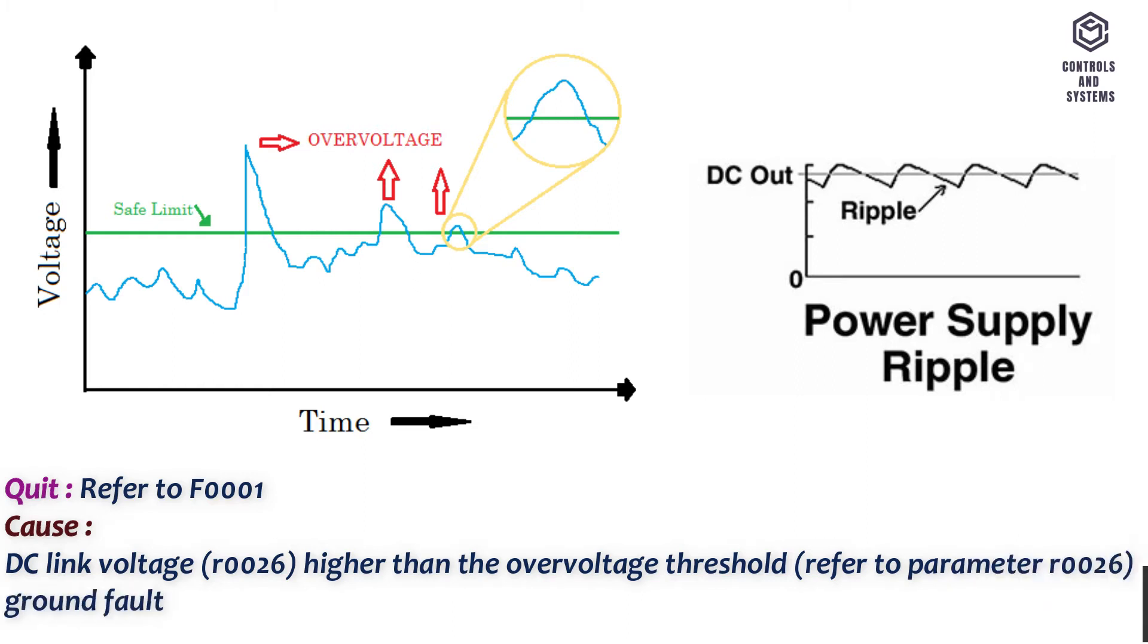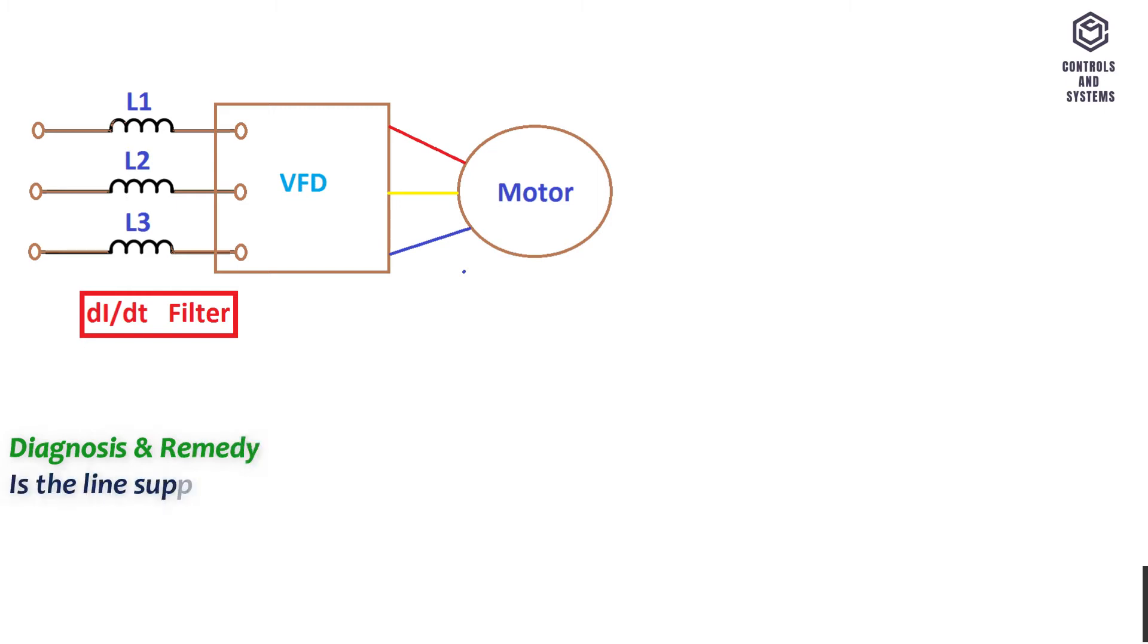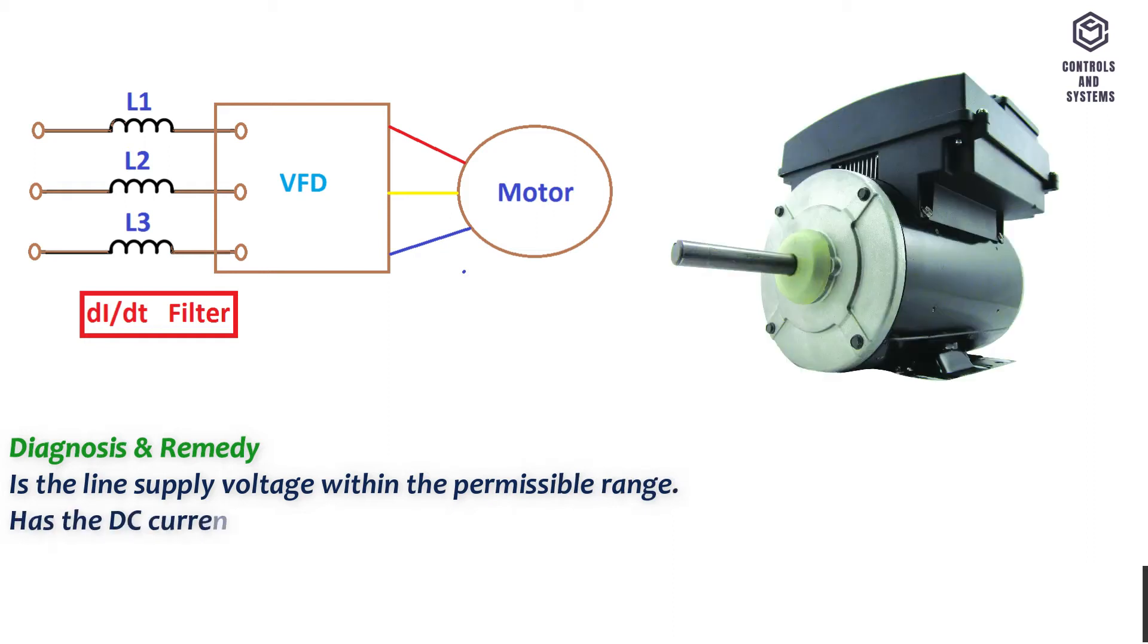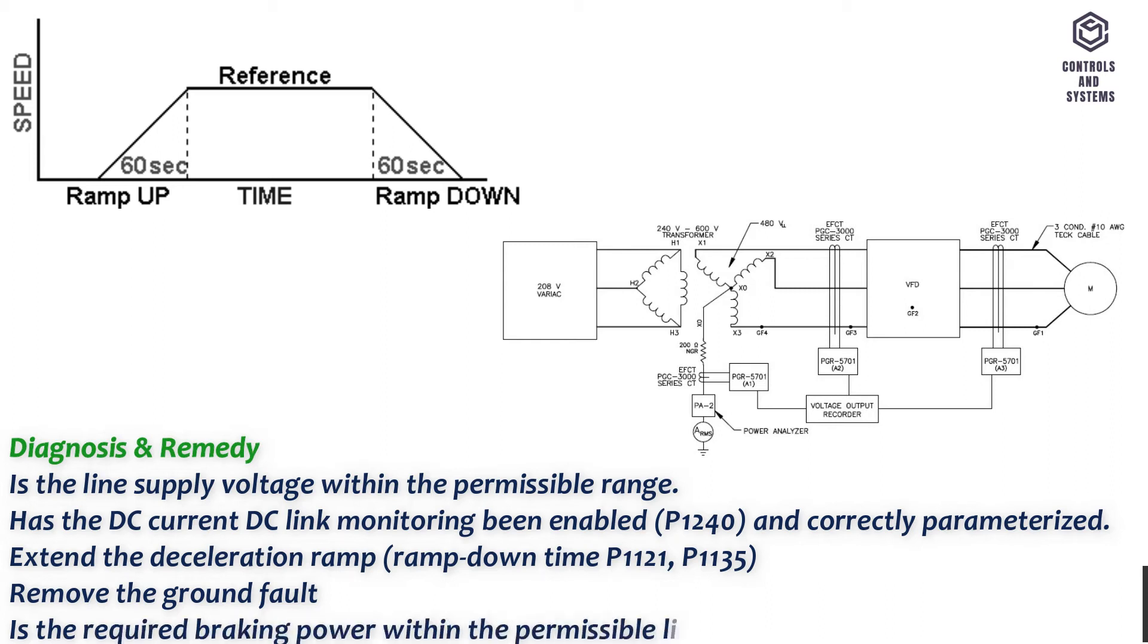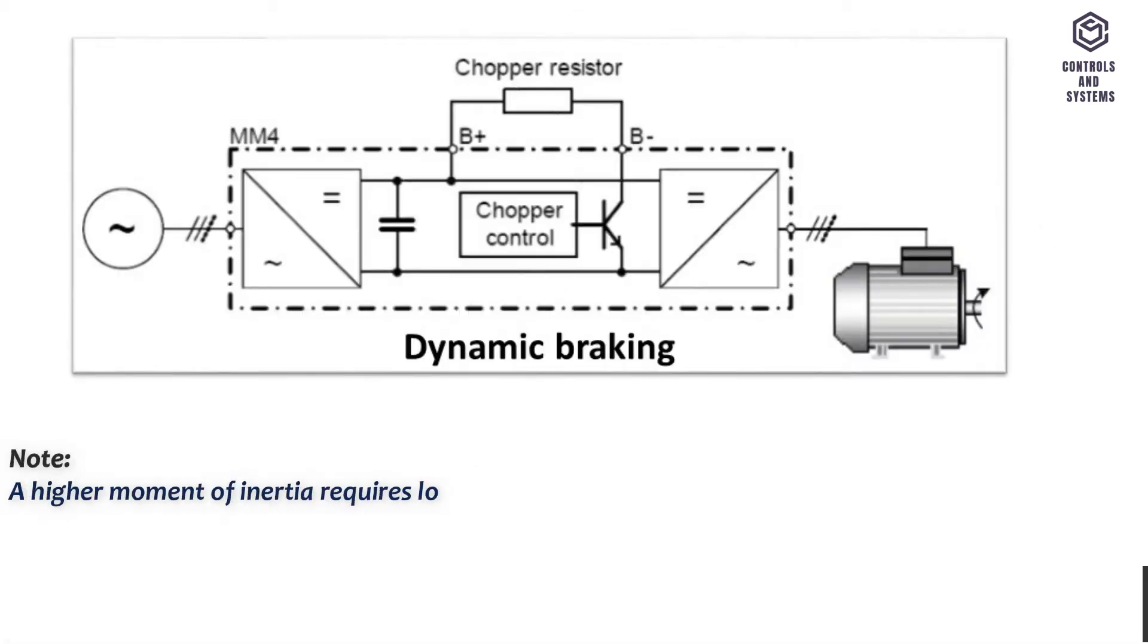Diagnosis and remedy: Is the line supply voltage within the permissible range? Has the DC link monitoring been enabled P1240 and correctly parameterized? Extend the deceleration ramp, ramp downtime P1121, P1135. Remove the ground fault. Is the required braking power within the permissible limits? Note: A higher moment of inertia requires longer deceleration times, if required, use a braking resistor.